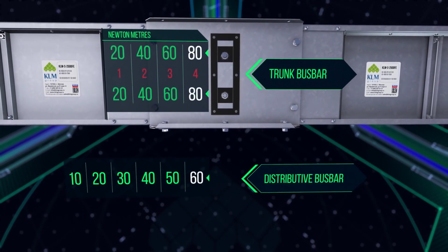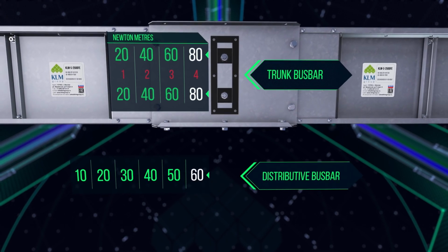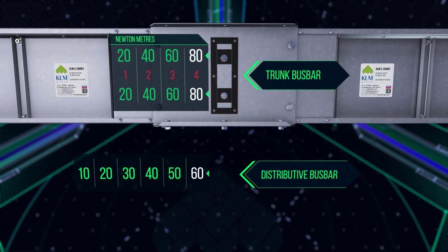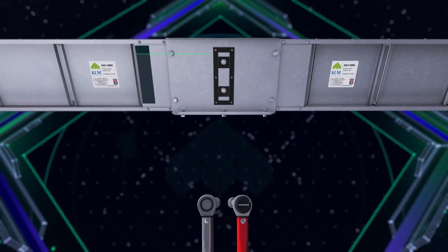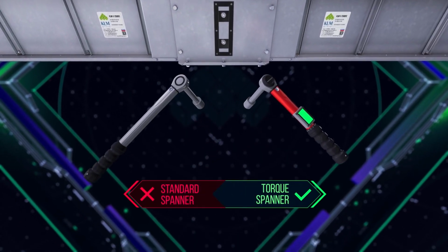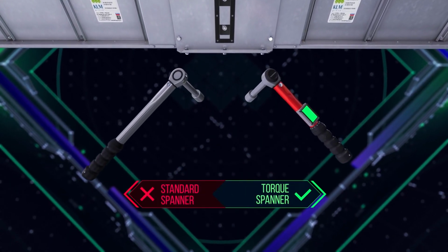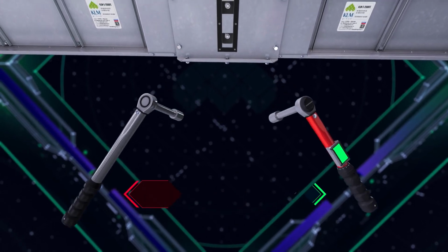For a distribution busbar trunking system, the clamping bolts must be tightened in increments of 10 Newton meters until a torque of 60 Newton meters is achieved. The clamping bolts must not be tightened using a standard spanner. Doing so may cause failure of the junction unit.